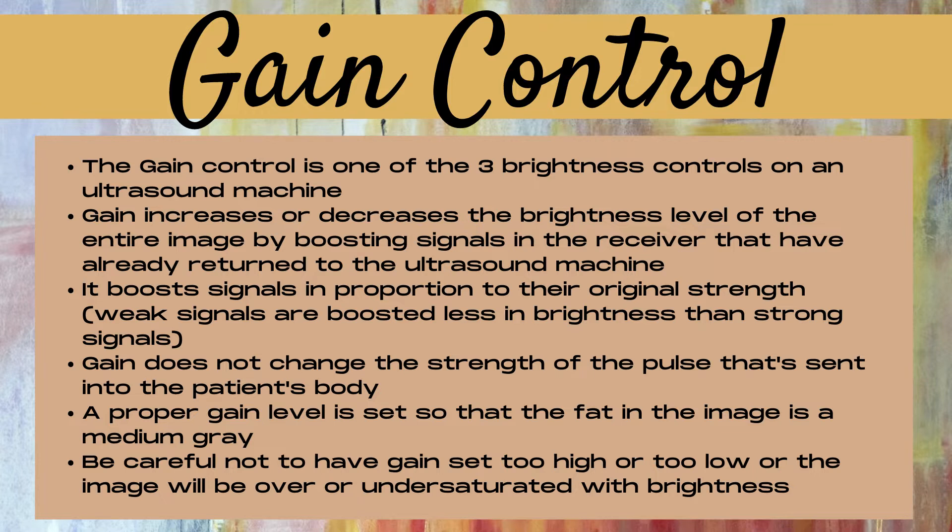Note that gain does not change the strength of the pulse that's sent into the patient's body, like the output power control does.